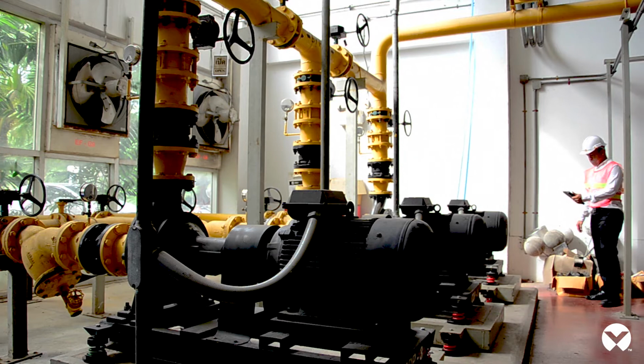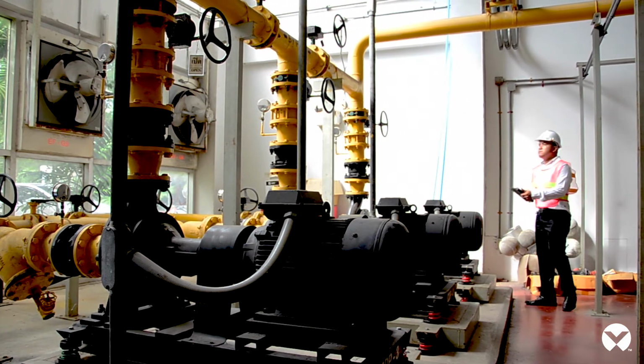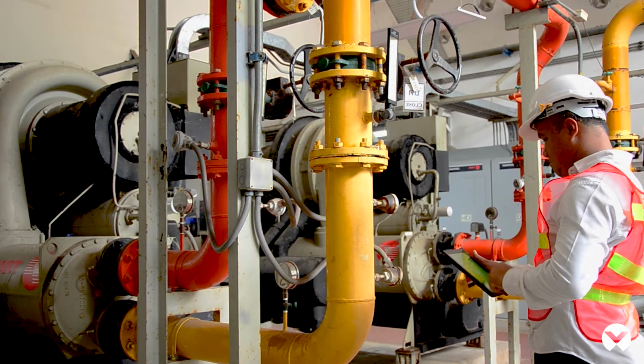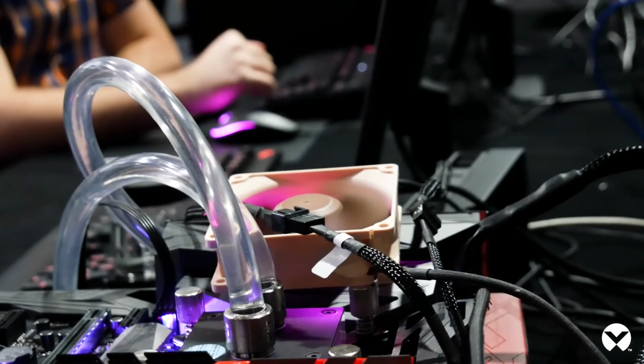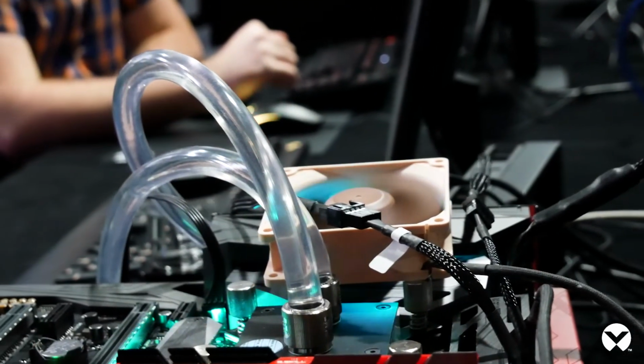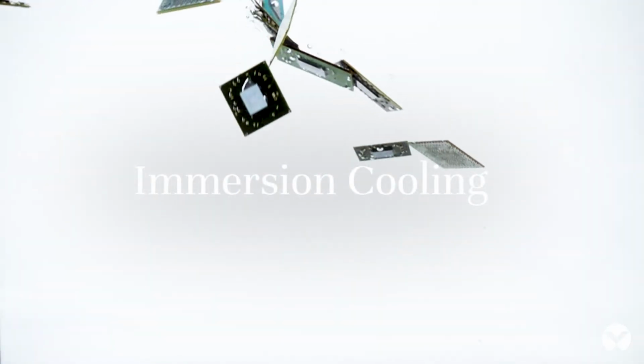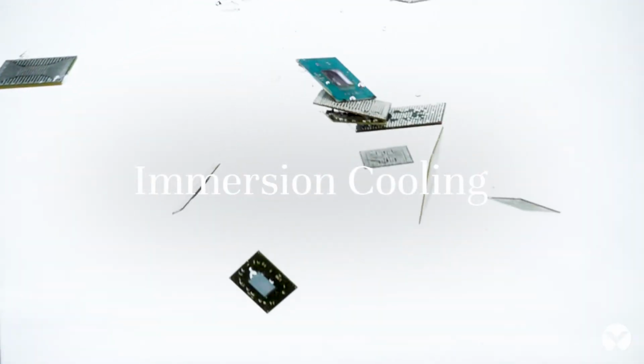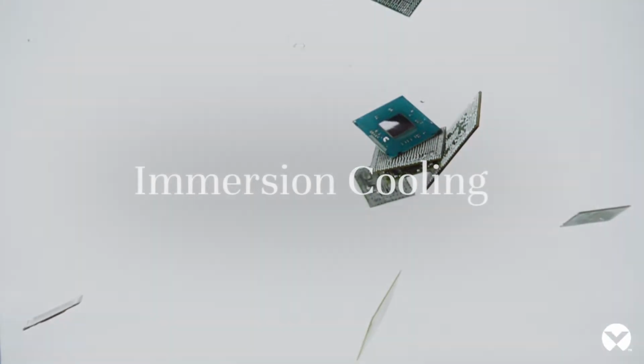So when we look at liquid-cooled machines, we're really seeing two types. One is where we're bringing a fluid or a liquid to a heat exchanger that sits directly on the chip or processor within the server, taking out probably 60–70% of the total server heat. The other method is to fully immerse the server into a dielectric fluid that removes all of the heat out of the server.